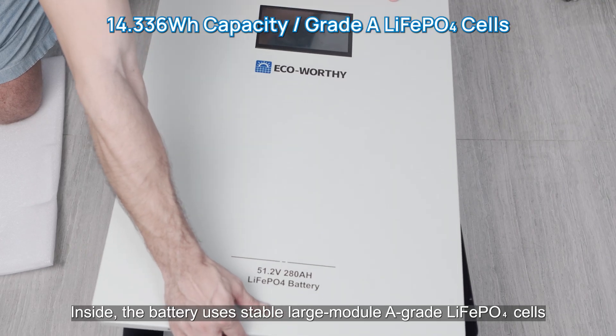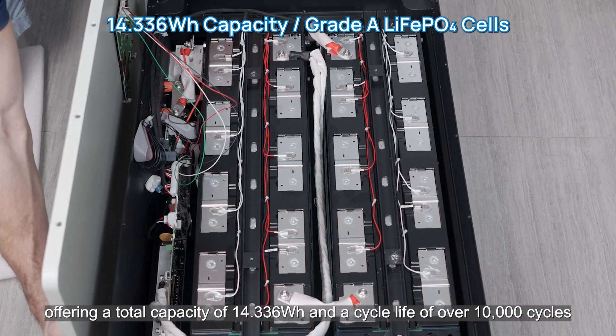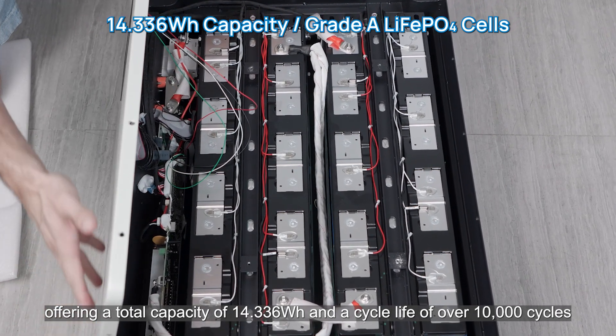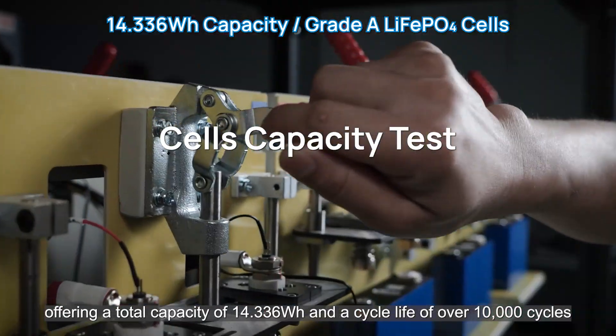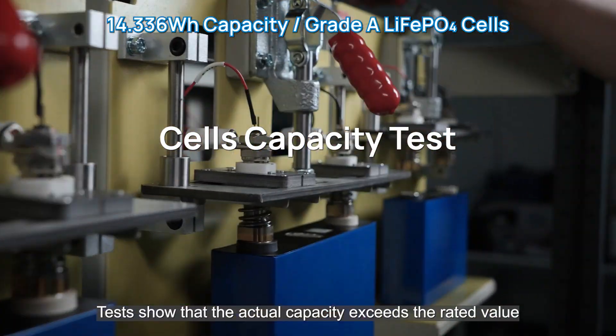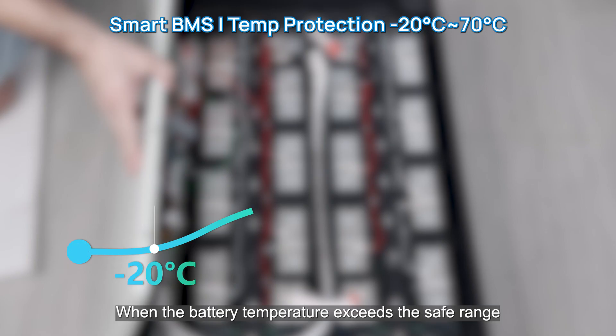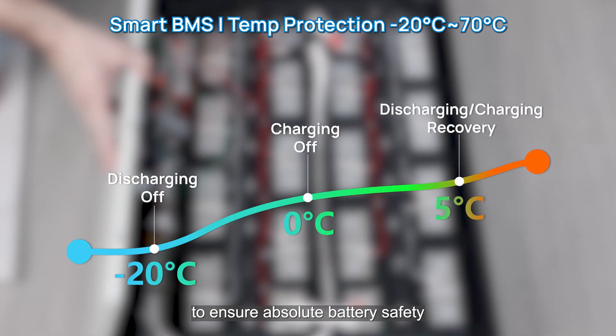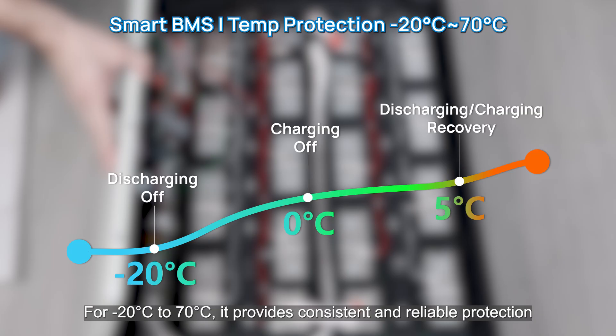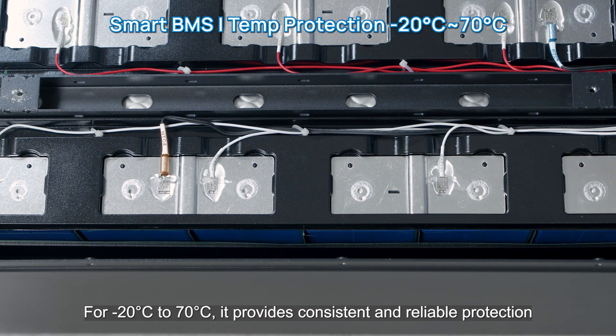Inside, the battery uses stable large-module A-grade lithium iron phosphate cells, offering a total capacity of 14.336 kWh and a cycle life of over 10,000 cycles. Tests show that the actual capacity exceeds the rated value, providing longer life and more stable power output. When the battery temperature exceeds the safe range, the intelligent protection mechanism immediately activates, ensuring safety from minus 20°C to 70°C.